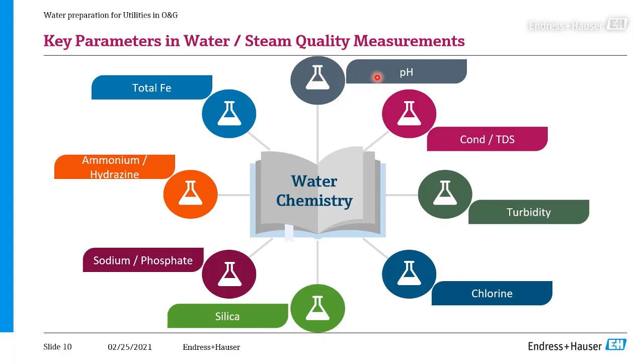One is pH. So in the pipe, to protect the pipe work, usually pH is maintained in the slightly alkaline range, so let's say from 7.5 to 9.2 pH. Conductivity should be in a certain range. Also turbidity is important for the makeup water treatment. It also gives us a little bit of an idea about the organic pollution. Chlorination is very important to protect the equipment.